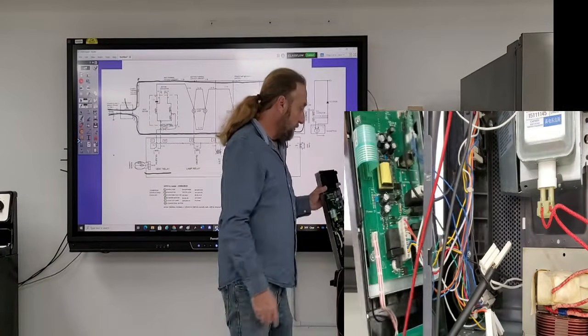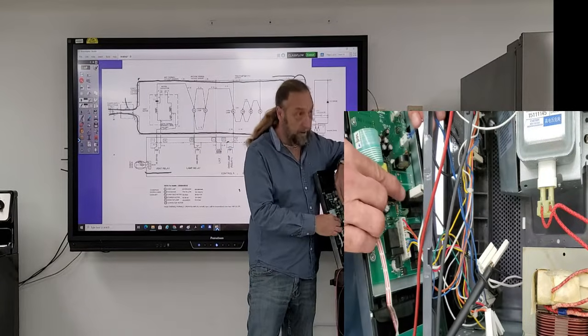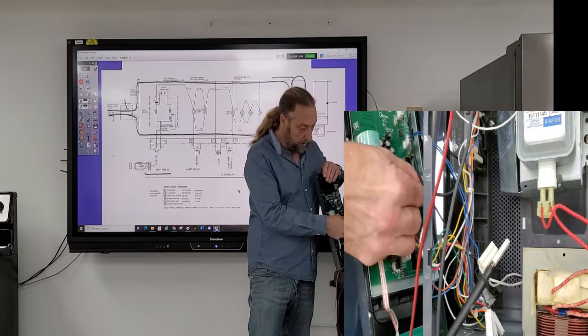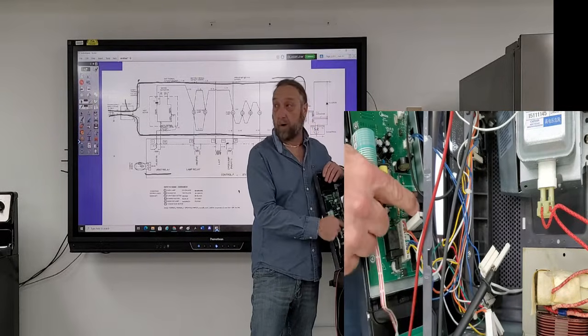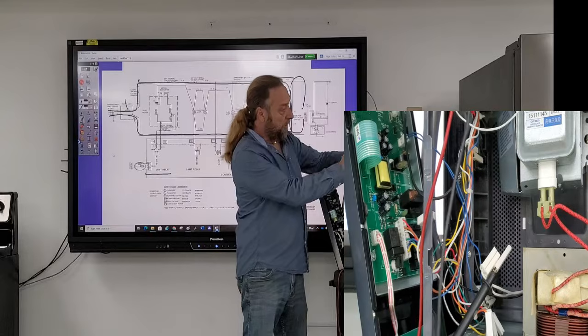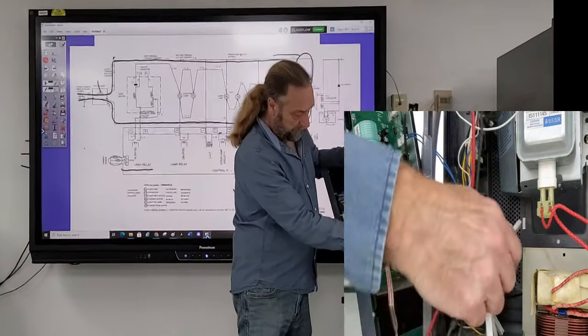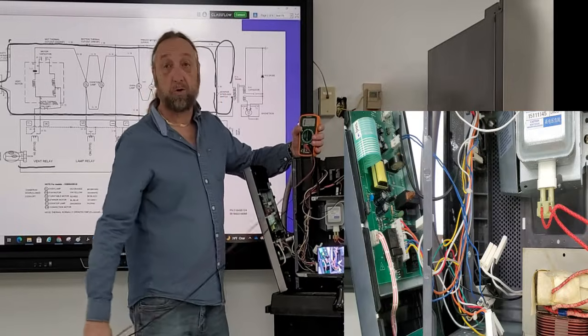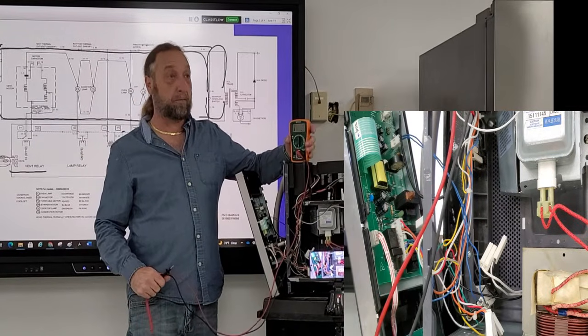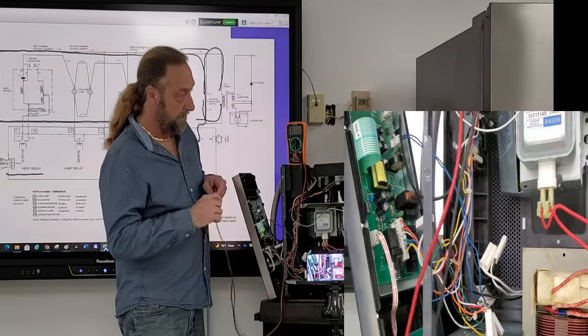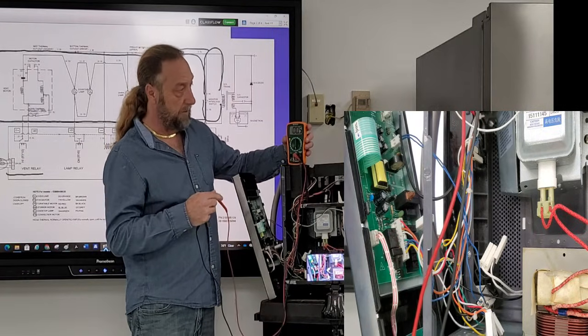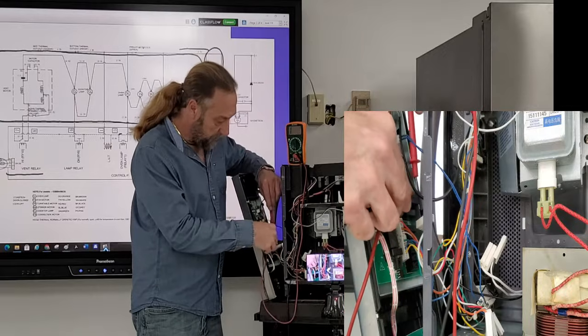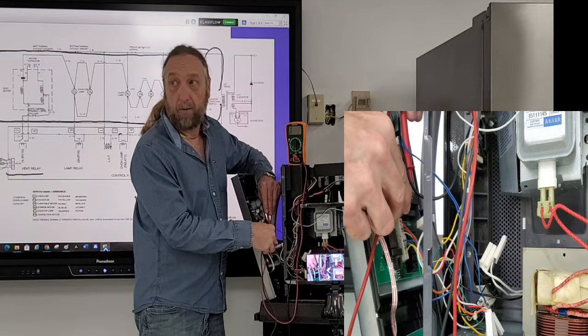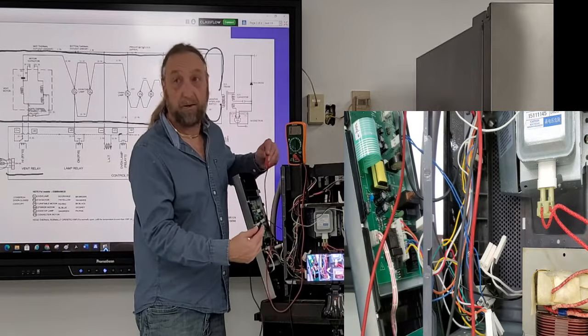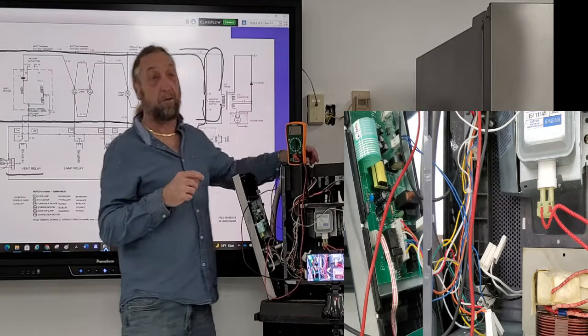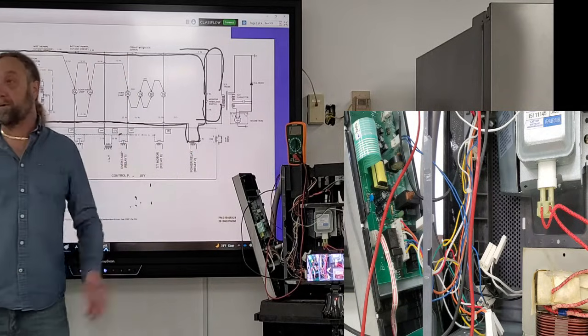That relay is this big black box here on the board. You just unplug the plug on that relay. You got two wires here. We go to ohms, and we touch those two terminals. What reading should I get right now? Here, I'm checking my meter, make sure it's working. I'm going to touch those two terminals on the meter. I got a reading, right? Meter didn't say nothing. That's good. Because when it's off, that relay should be open.